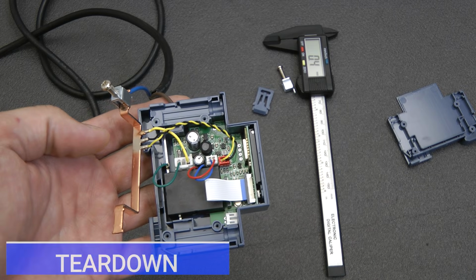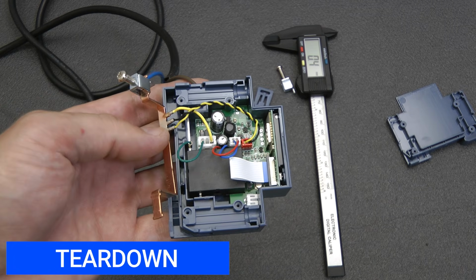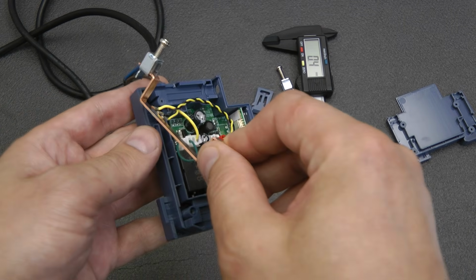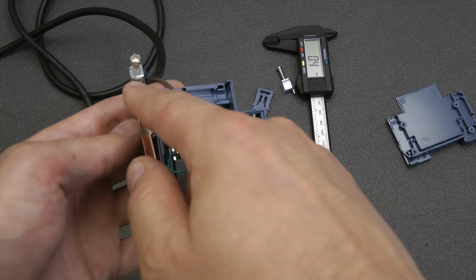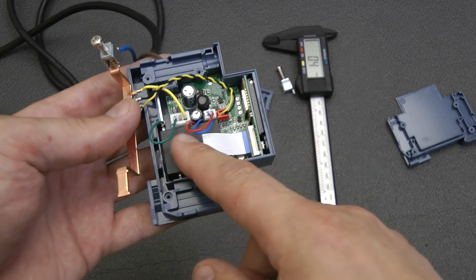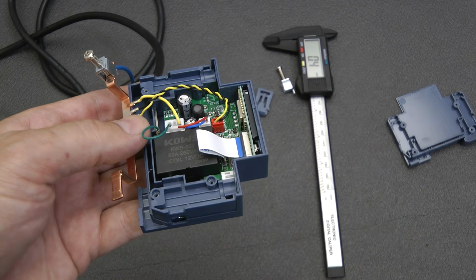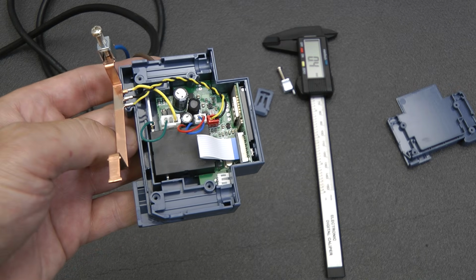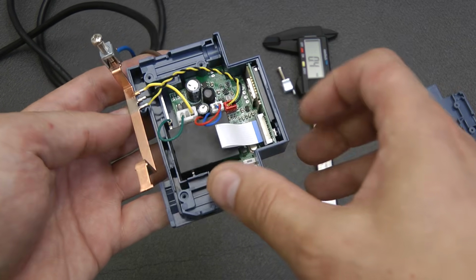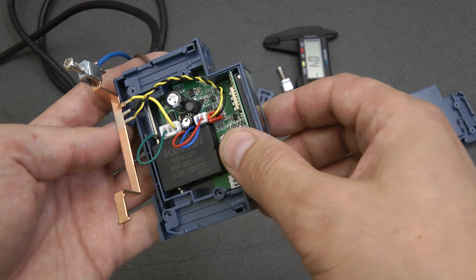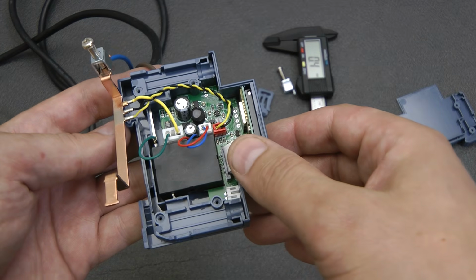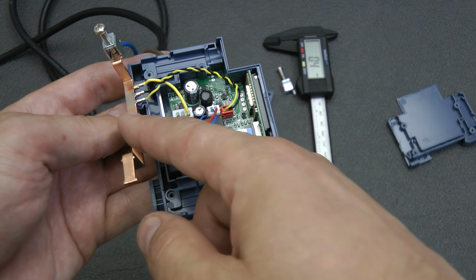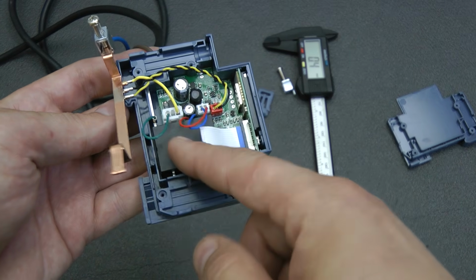Under the cover, everything is quite simple. The neutral here goes through a separate copper busbar 1 mm thick, which directly connects the input and output terminals. The phase is controlled by a separate KWS-303 electromechanical relay. The housing states 63 amps, 250 volts AC, and a 12-volt coil. So the switching here is single pole. When turned off, only the phase is disconnected, while the neutral remains connected.